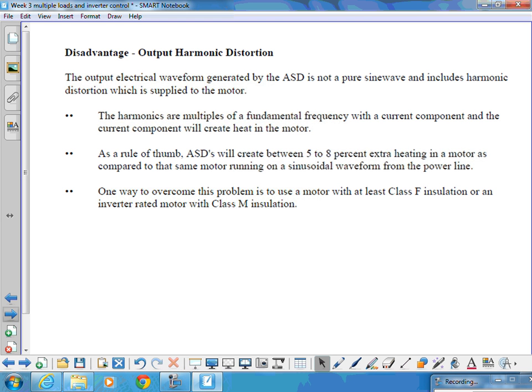As a rule of thumb, ASD's will create between 5 to 8% extra heating in a motor compared to the same motor running on a pure sinusoidal waveform. One way to overcome this problem is to use a motor with at least class F insulation, or an inverter rated motor with a class M insulation. So we're talking about the extra heat being more likely to break the insulation down.